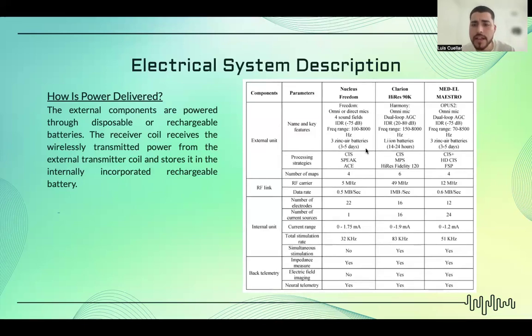This is why you see these lengthy numbers, like 3 to 5 days of battery power. The Clarion HiRes 90K is on the lower end, probably not the best. 14 to 24 hours is not ideal for somebody who needs the device constantly. Another interesting fact we can see through this chart is the number of electrodes on each one. If you notice, the lower the number of current sources, the more electrodes there are. The Nucleus Freedom has one current source and 22 electrodes.